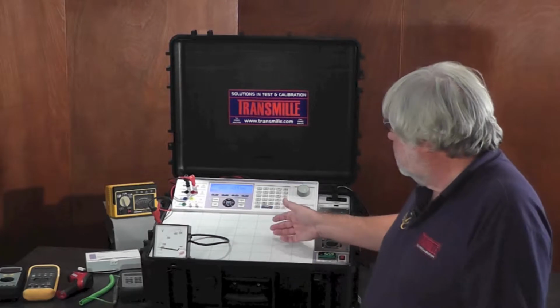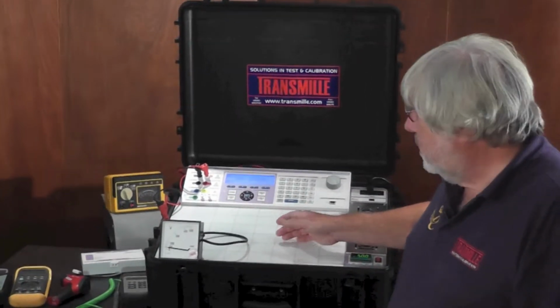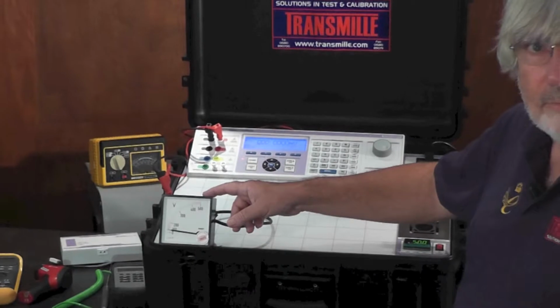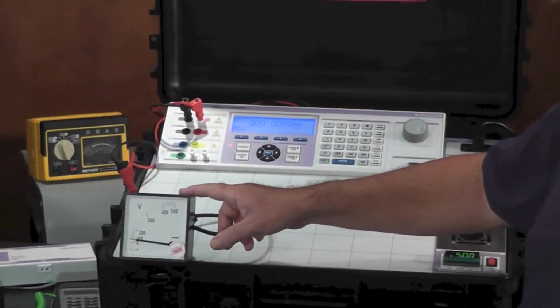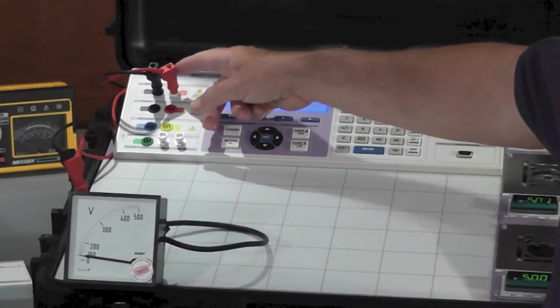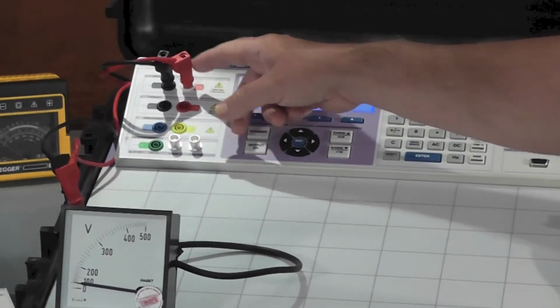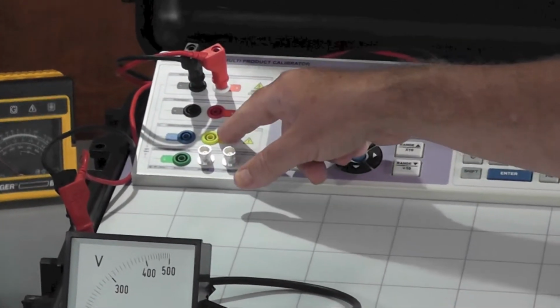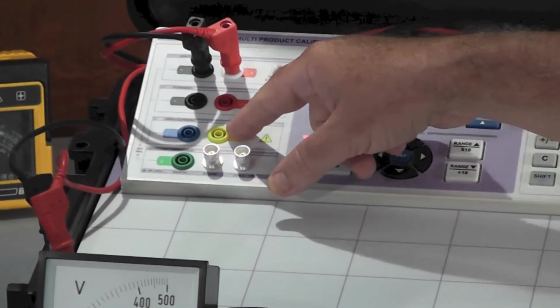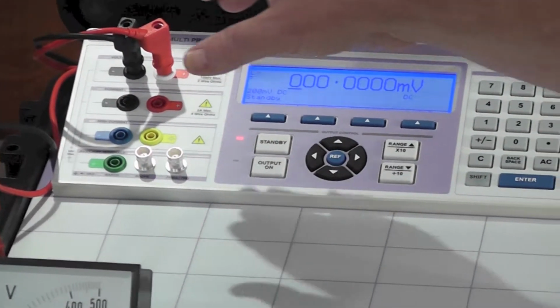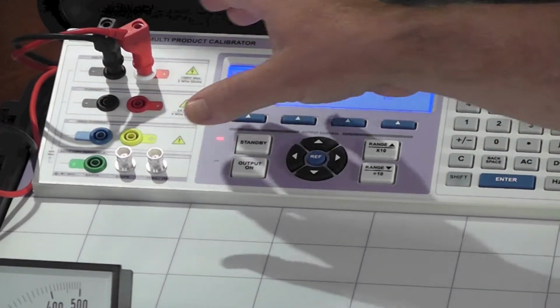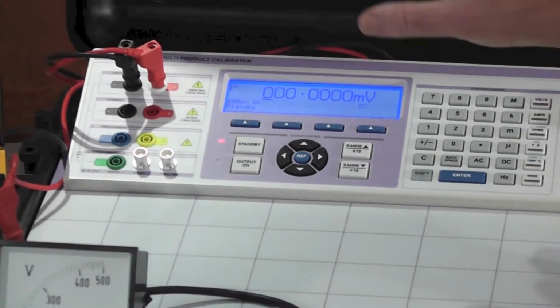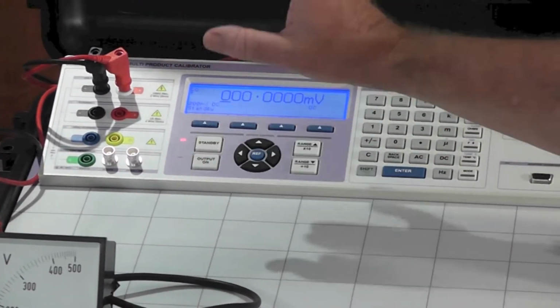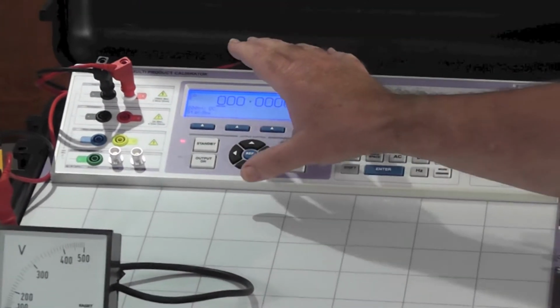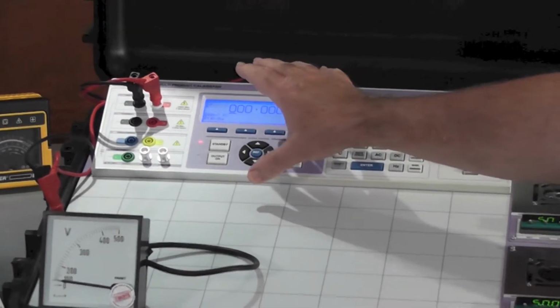It's that simple. The 9000A has got plenty of drive, more than enough to drive older analog panel meters, even moving iron meters like this. You can drive up to 1000 volts at 20 milliamps, that's AC or DC. You can drive up to 30 amps, AC or DC. And you've got resistance right up to 1G ohm. The capacitance, you know, options for inductance, temperature PRT, frequency 10 megahertz, a very wide ranging calibrator.